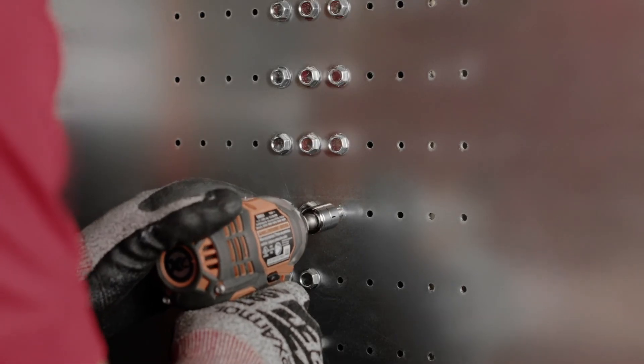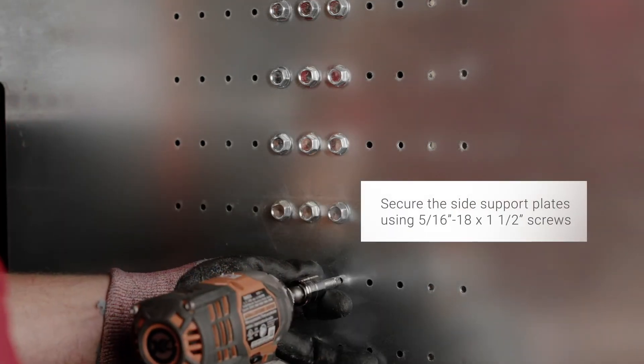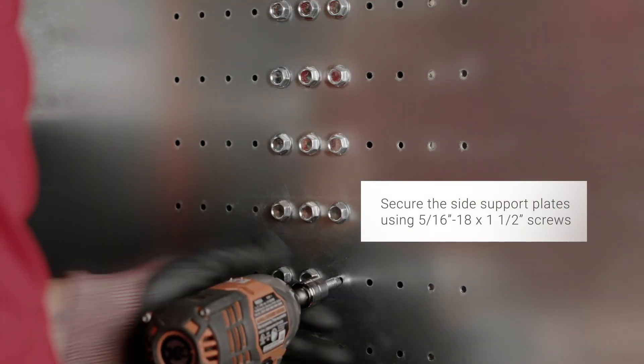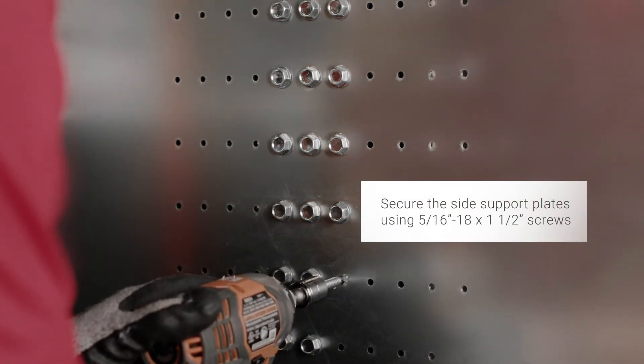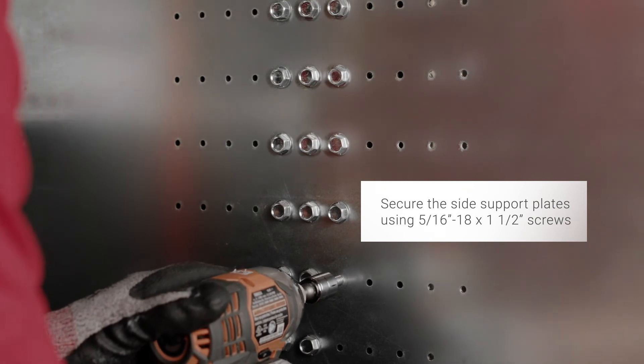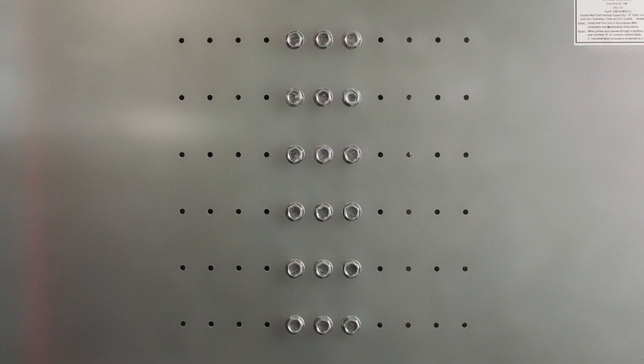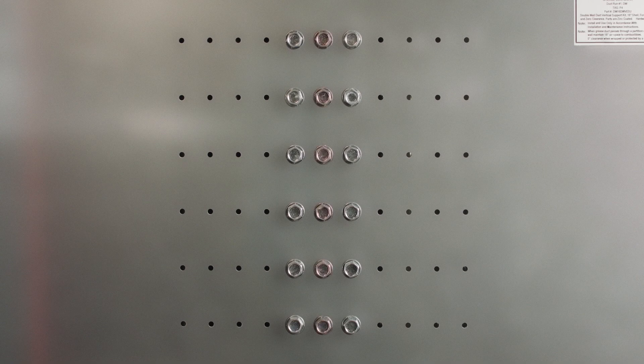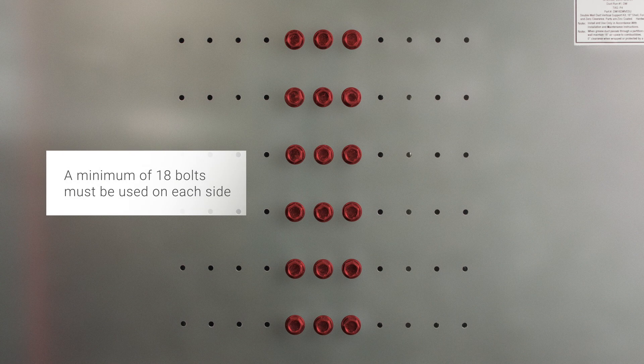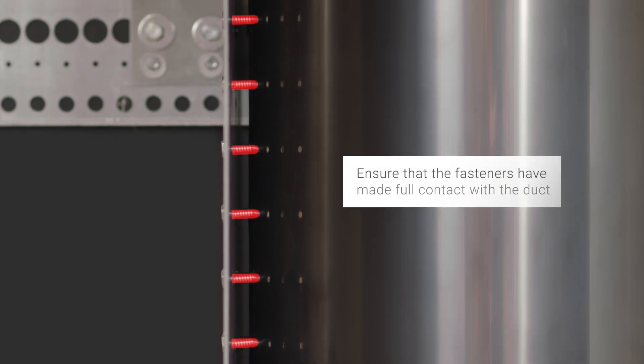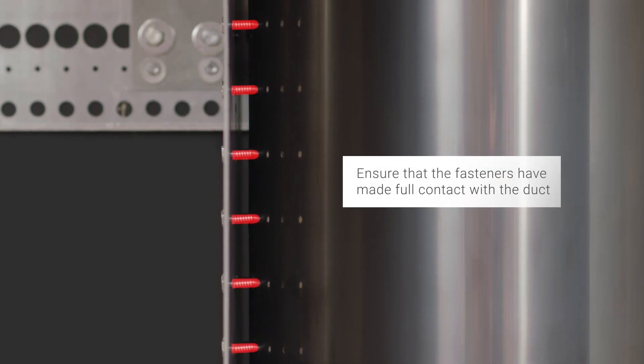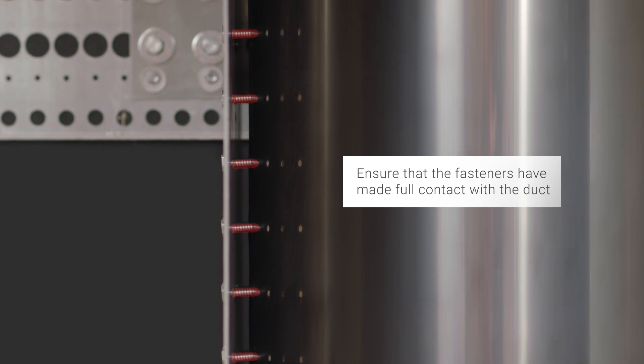Secure both side support plates to the outer duct shell using the five sixteenths 18 by one and a half inch self-drilling screws. Use the guide holes to locate the shell center and fill all holes center, center left and center right. A minimum of 18 screws must be used on each side of the duct. Ensure that the fasteners have made full contact with the duct.